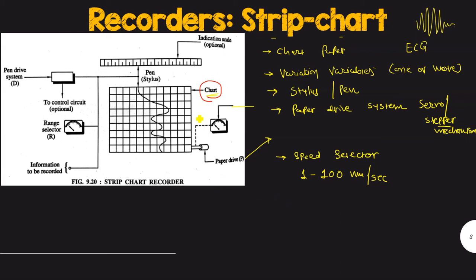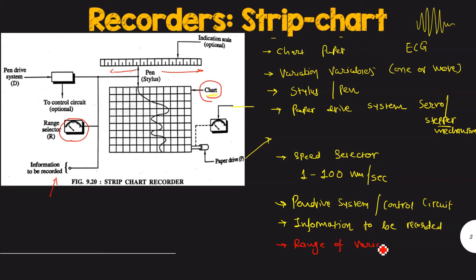There exists another drive system which is nothing but a pen drive system and a control circuitry for pen drive system which is then connected to the variable or the information. As the input quantity to this pen drive system which is to be recorded, accordingly the pen or stylus will attain the horizontal movement and will continuously plot the data on the chart. The range selectors which is shown over here are used to select the range of variable or process parameter.